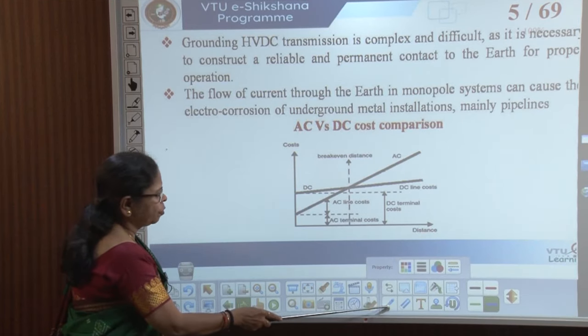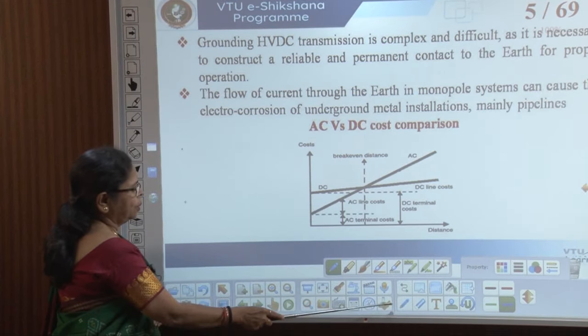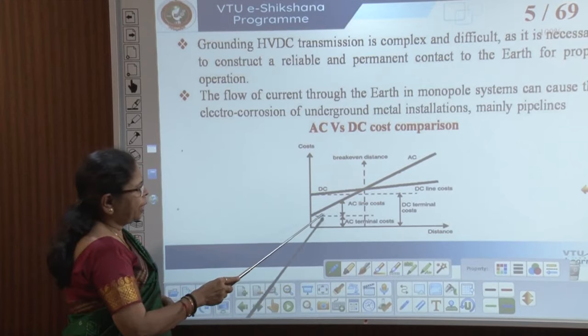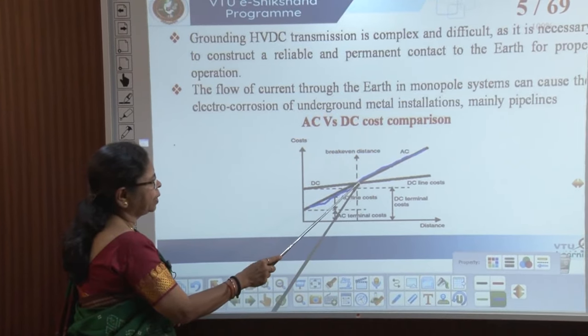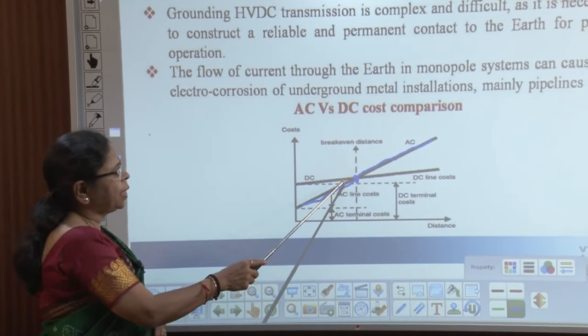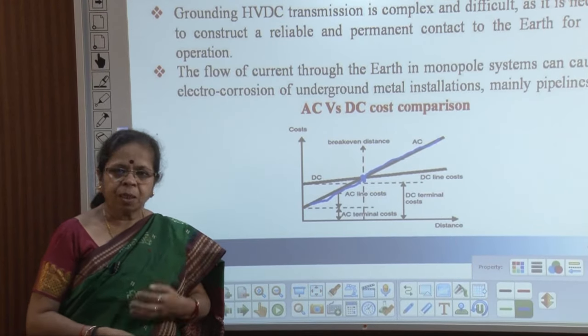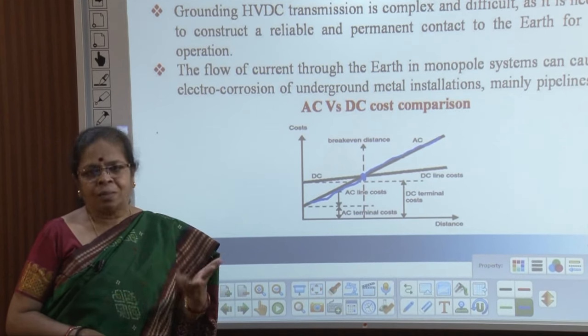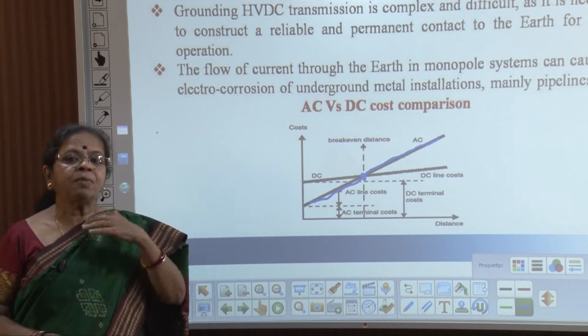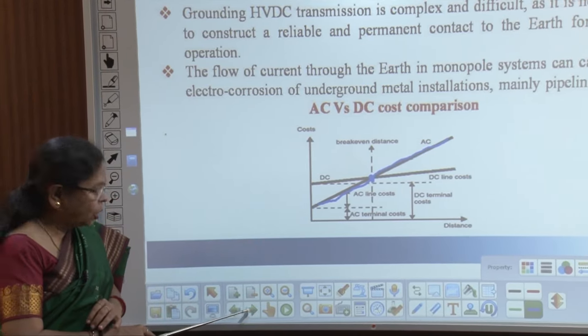Now, looking at a cost vs. distance graph, the x-axis is the distance of transmission and the y-axis is the cost. The AC line and DC line intersect at roughly 600 kilometres. Below 600 kilometres, AC lines are cheaper. Beyond 600 kilometres, DC lines become cheaper, as the cost advantage of HVDC offsets the other HVDC costs. So wherever the transmission distance is more than 600 kilometres, HVDC transmission provides a viable alternative to AC transmission.